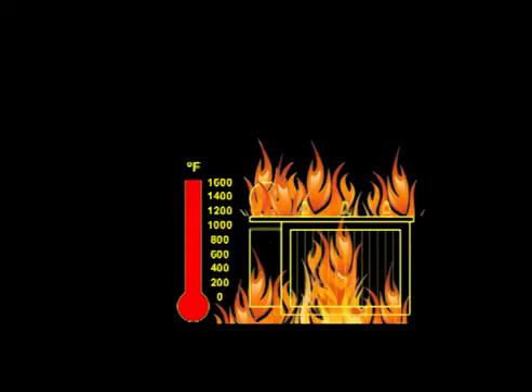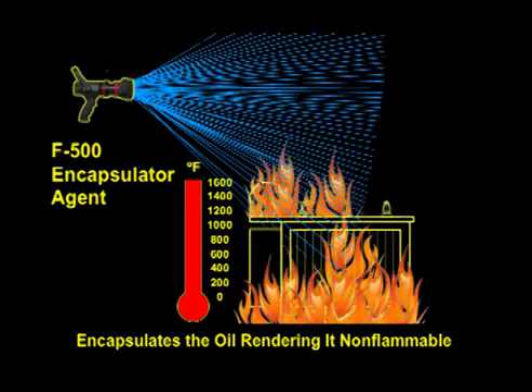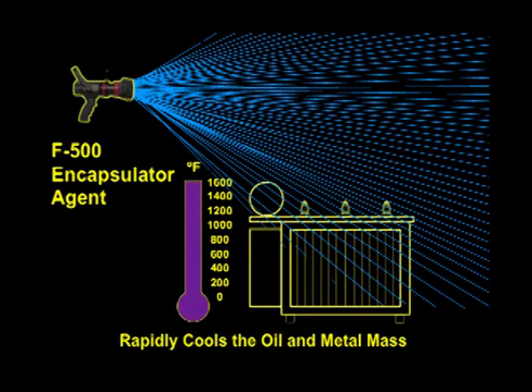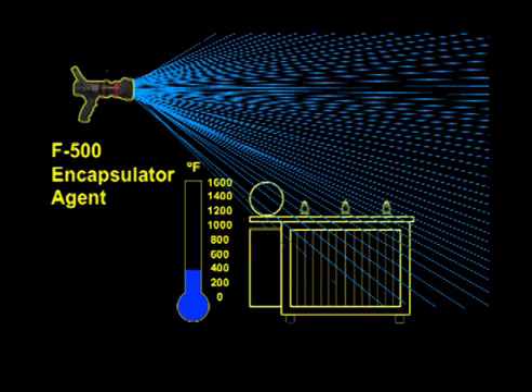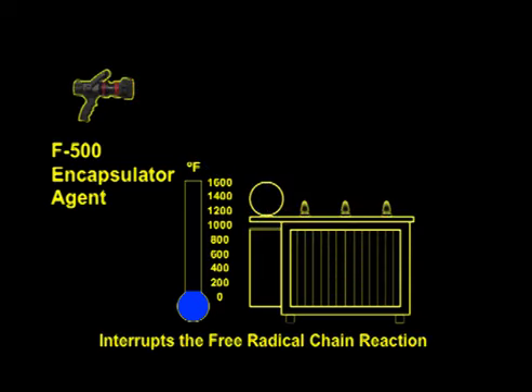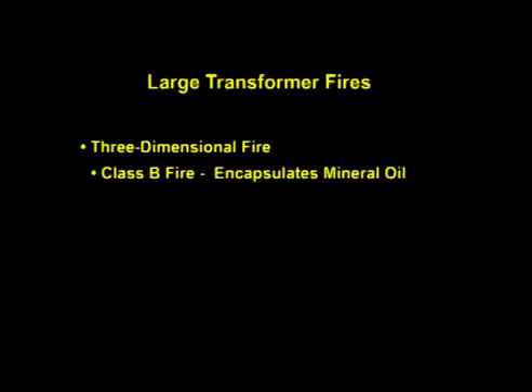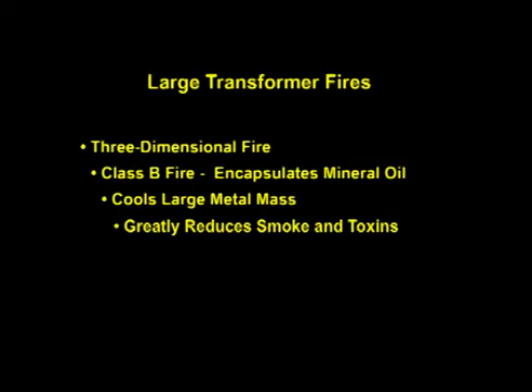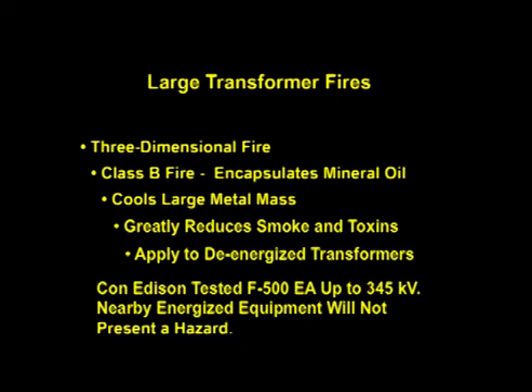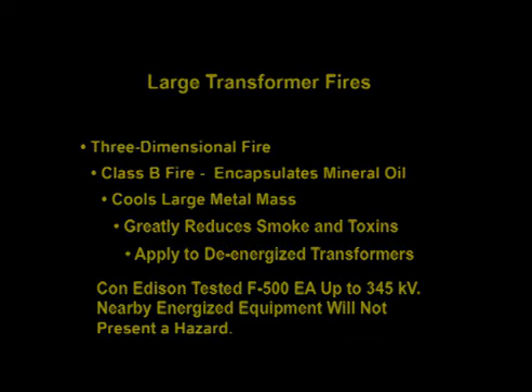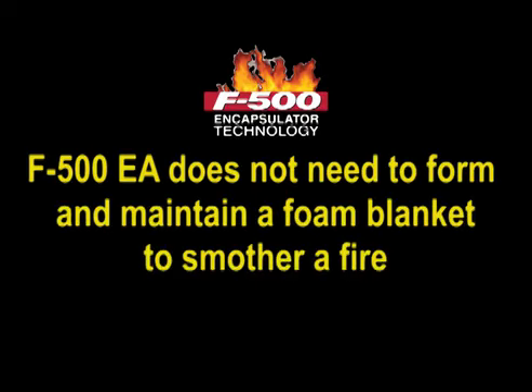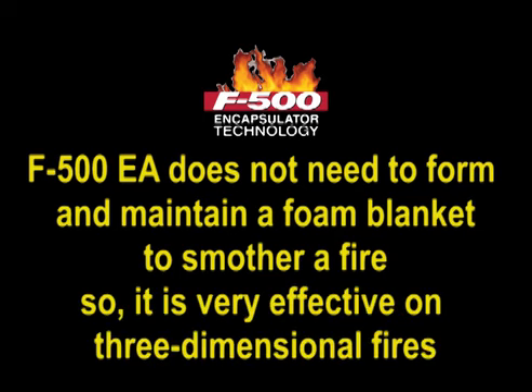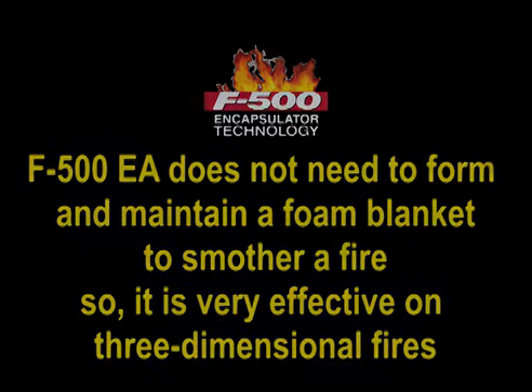F500 encapsulator agent is a 3-dimensional Class B fire suppression agent. The F500 EA rapidly cooled the hot oil and metal, reducing the temperature below the flash point of the oil. Simultaneously, the F500 EA encapsulated the oil, rendering it non-flammable. It also interrupted the free radical chain reaction, eliminating the heavy black smoke. Very little water and agent was used with F500. F500 EA does not rely on the formation and maintenance of a foam blanket to smother a fire, so it is very effective on 3-dimensional fires like transformers.